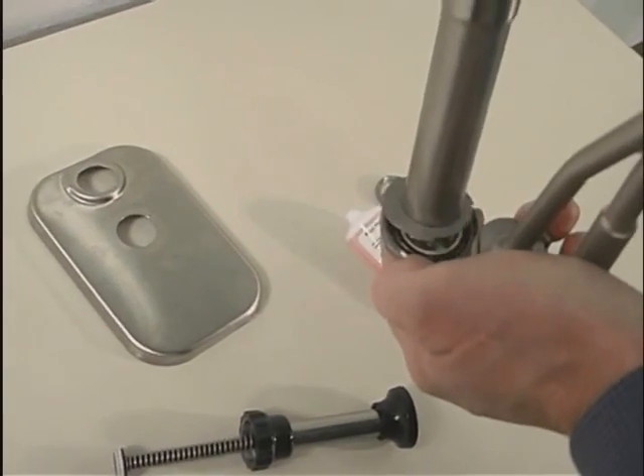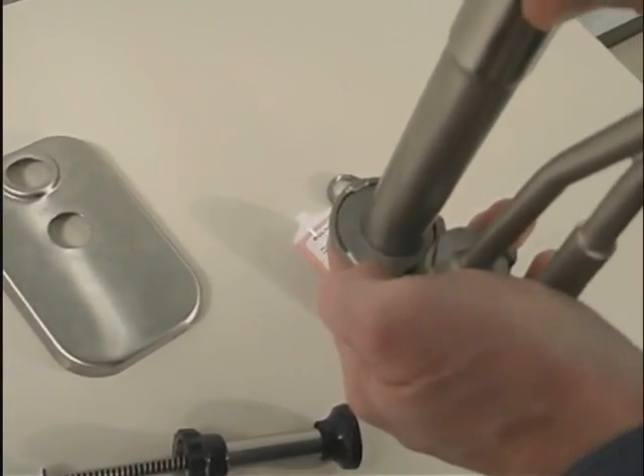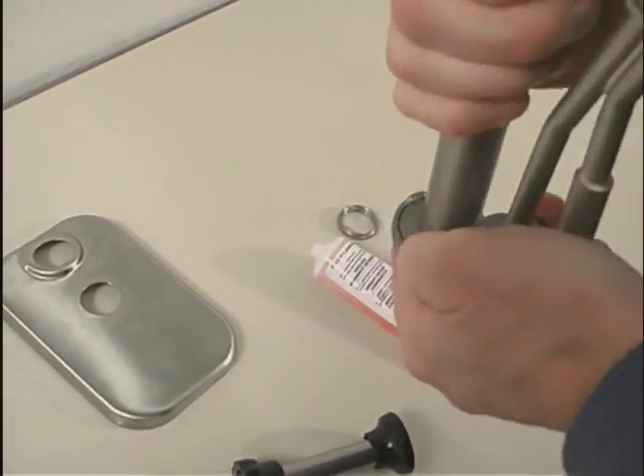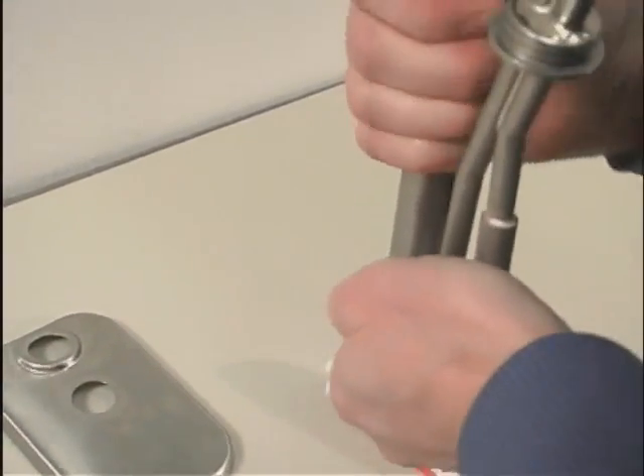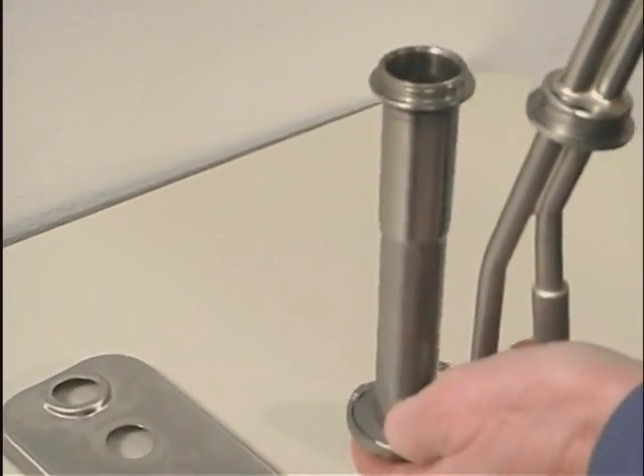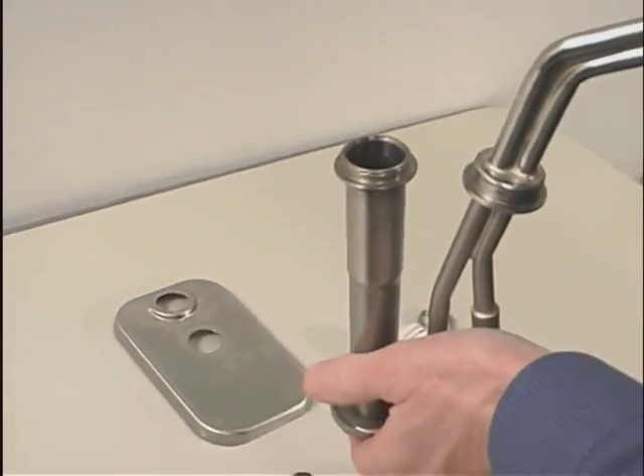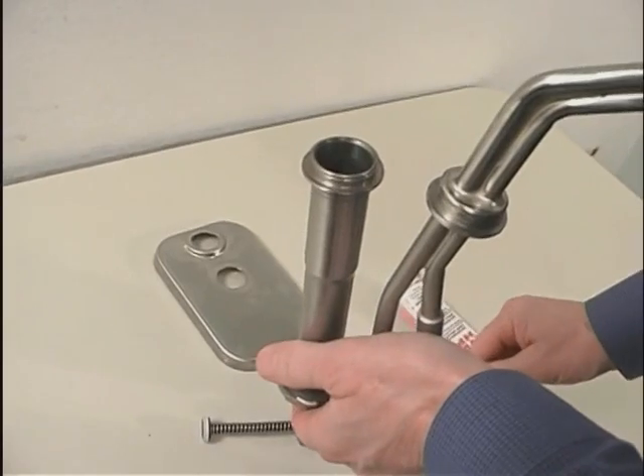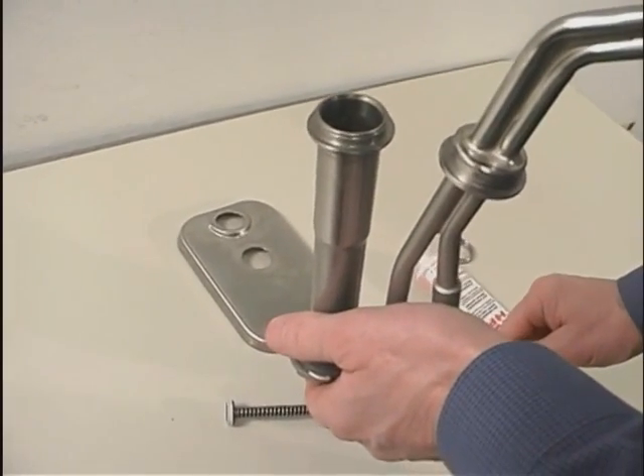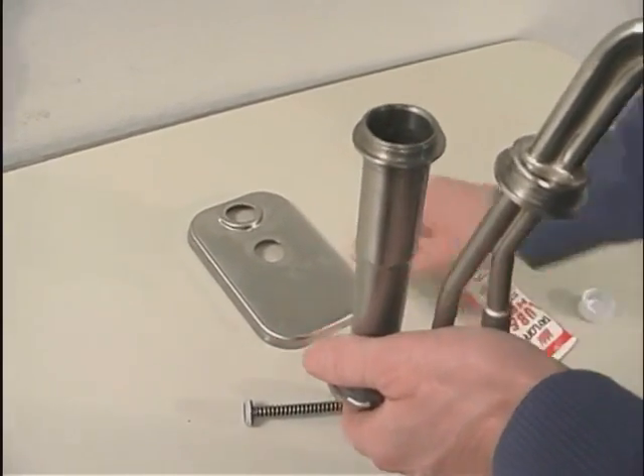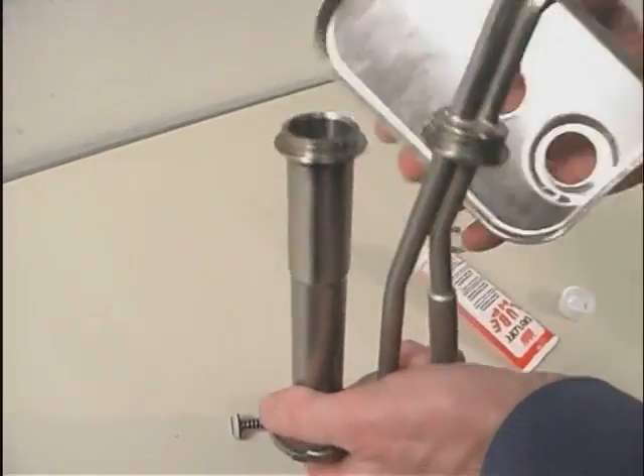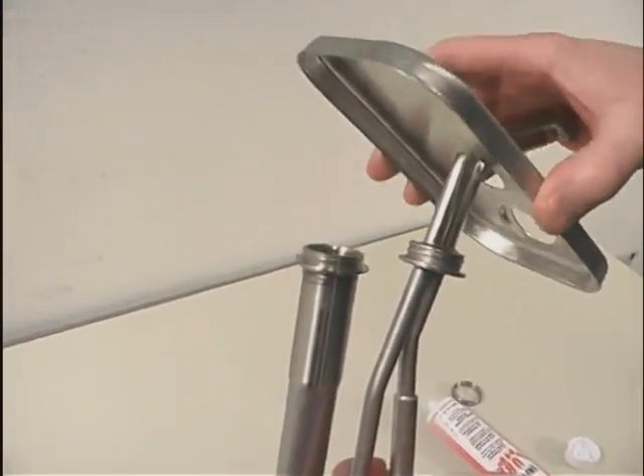Install the cylinder onto the larger opening in the valve body by tilting the cylinder away from the discharge tube and sliding the widest section of flange under the center locking groove on the valve body. Align the tabs on the cylinder with the locking grooves on the valve body. Turn the cylinder clockwise until the tabs fully engage into the locking grooves on the valve body.